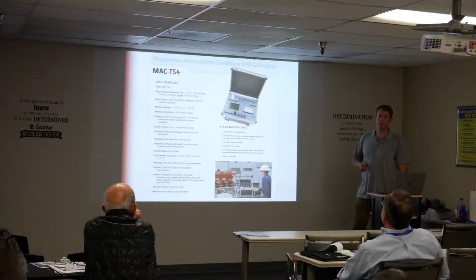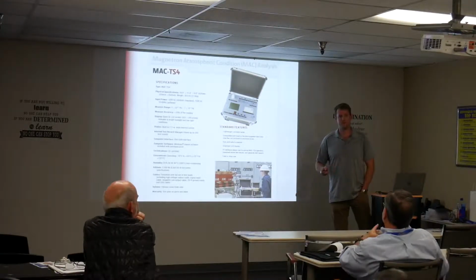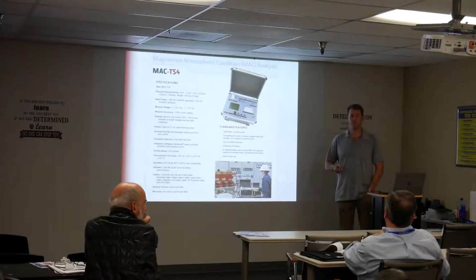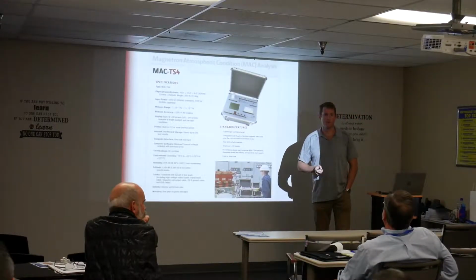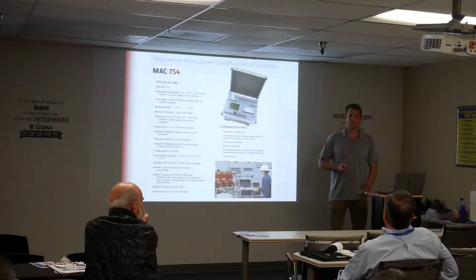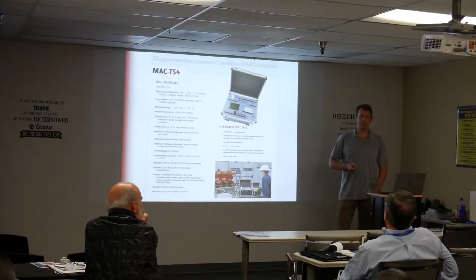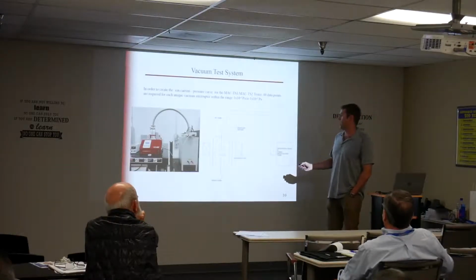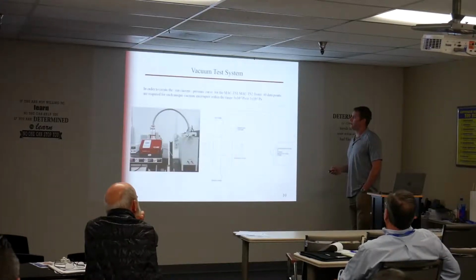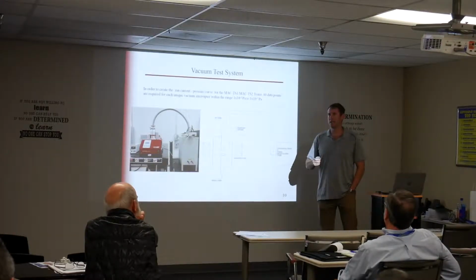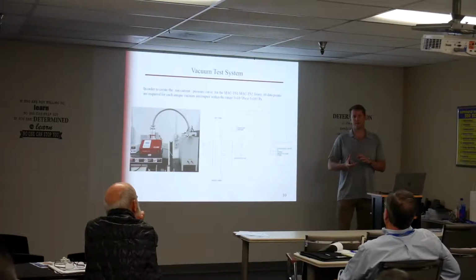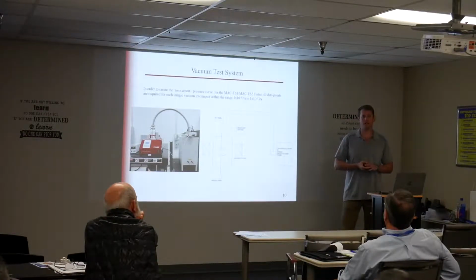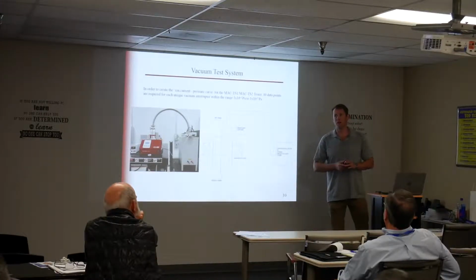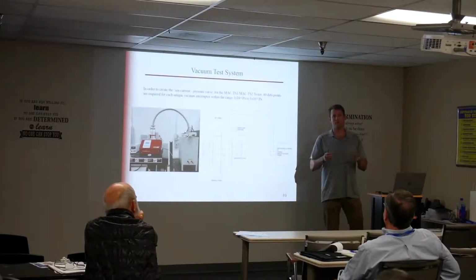So if we were to tell you we had a bottle, certain part number by Siemens, you would probably have that curve, so by measuring current, you can tell us what the pressure is. We did think at the beginning we were going to have to make a curve for each manufacturer. But after testing thousands of them, it doesn't really matter who makes them. Based on the diameter, based on the ratings, they all kind of use the same basic geometry.